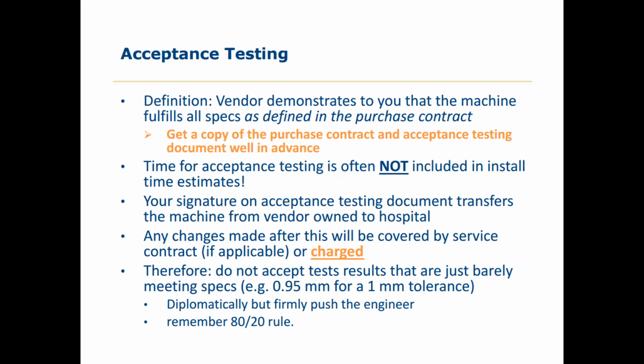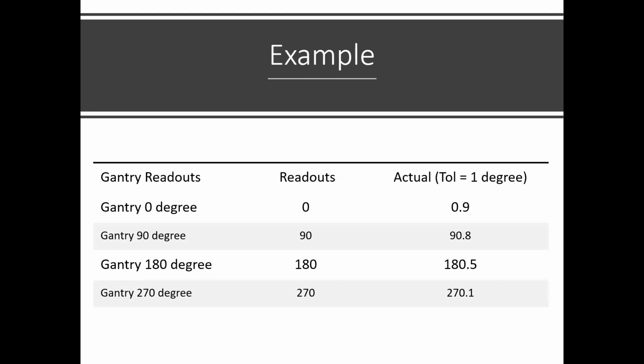And as a rule, we should not be accepting our machines at marginal values. For example, the tolerance for a gantry is 1 degree, and if we end up with a value of 0.9 in acceptance, we should certainly ask the engineer to bring this down. Otherwise, the moment he flies back, the next day my value will be more than 1 degree, and I will end up with troubles right at the start.